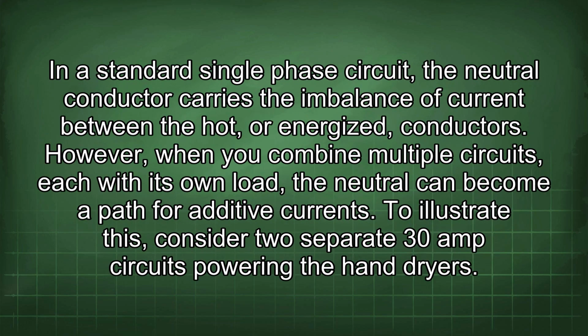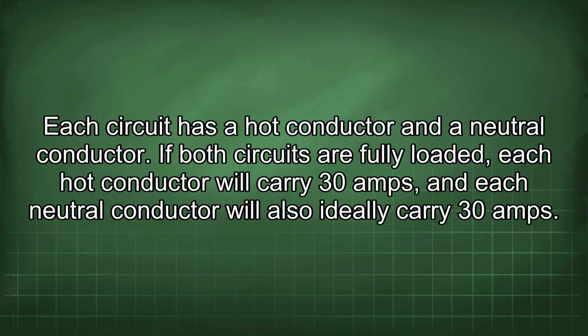In a standard single-phase circuit, the neutral conductor carries the imbalance of current between the hot, or energized, conductors. However, when you combine multiple circuits, each with its own load, the neutral can become a path for additive currents. To illustrate this, consider two separate 30 amp circuits powering the hand dryers. Each circuit has a hot conductor and a neutral conductor.